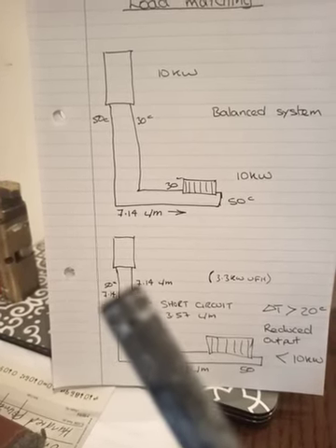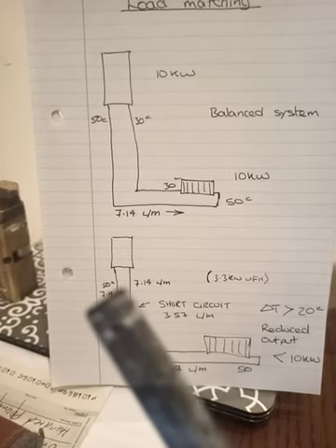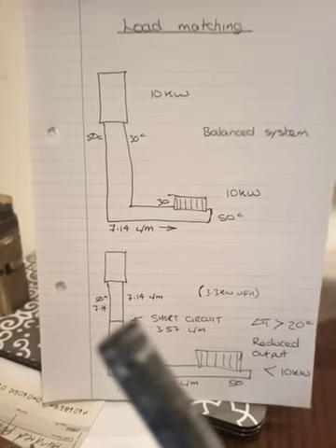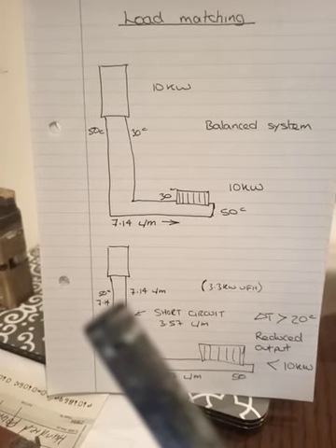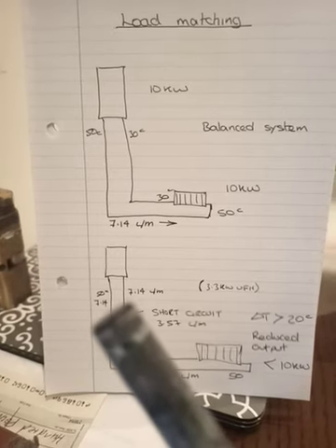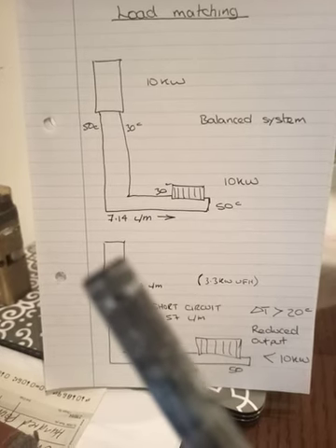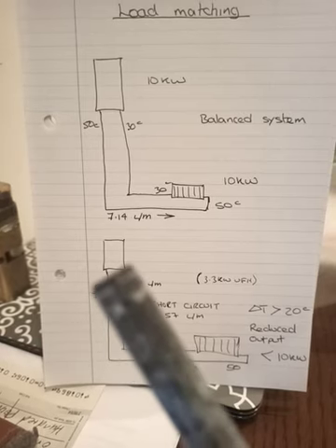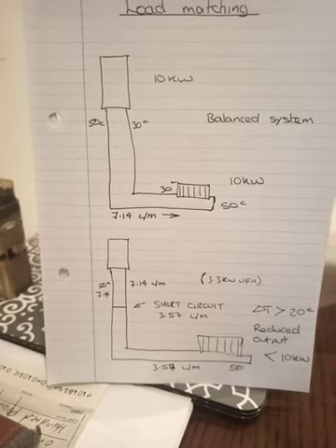And the temperature coming back to the boiler will no longer be delta T20 across here. It will be higher. We will have a raised return temperature. And I know that's contentious. But the return temperature will be higher with this bypass. Now that boiler is still targeting 50 degrees, so the boiler will modulate down. We'll have a lower delta T, a raised return temperature, and the boiler will output the matching requirement for this radiator.